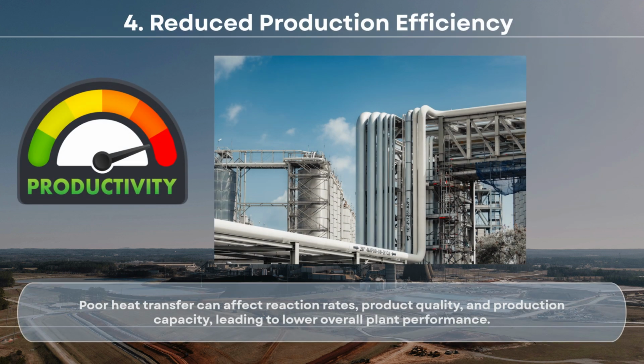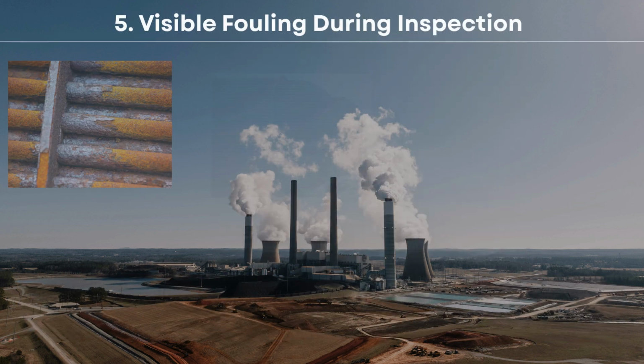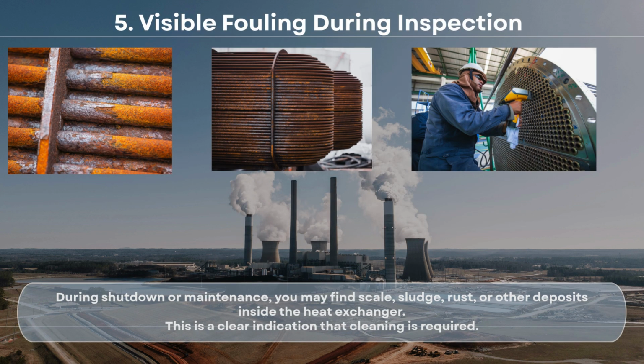Reduced production efficiency. Poor heat transfer can affect reaction rates, product quality and production capacity, leading to lower overall plant performance. Number 5. Visual fouling during inspection. During shutdown or maintenance, you may find scale, sludge, rust or other deposits inside the heat exchanger. This is a clear indication that cleaning is required.